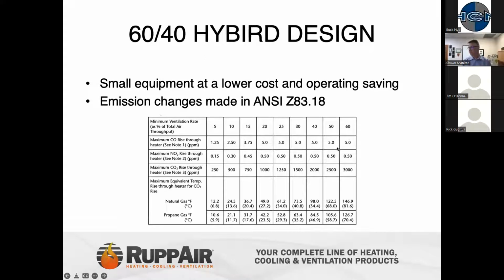Down here is the chart that I was just referring to as far as the capability of temperature rise. What this number across the top here equates to is the amount of outside air: 20% outside air, 40% outside air, 50% outside air. And basically what the ANSI standards did back in 2002 or 2003 is look at how much fresh air we need to introduce to a space with a direct fire unit to have safe combustion, safe emissions into the space. And that's basically what this did. So at 20% outside air, we're limited to 49-degree temperature rise. At a 40, we're limited to 98, 50, 122. And you can see the more fresh air you bring in, the more temperature rise capability you'll have.